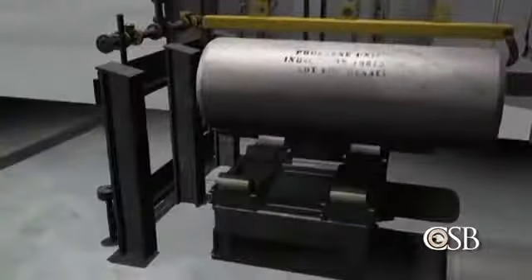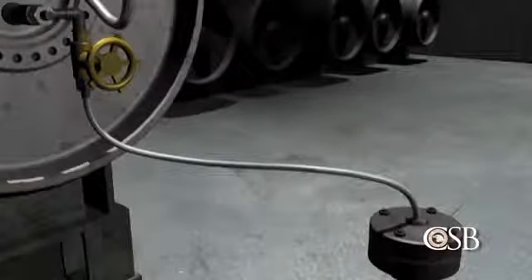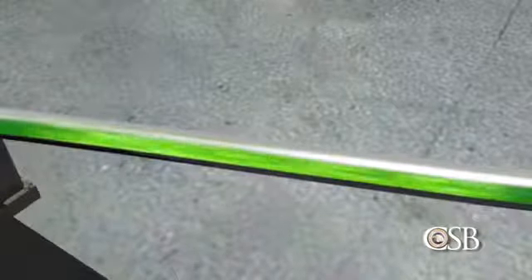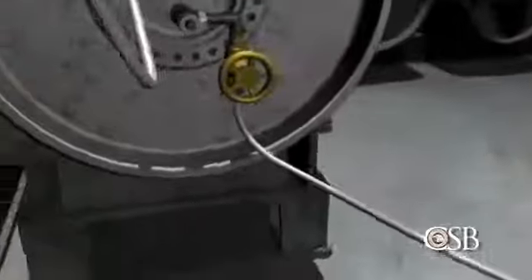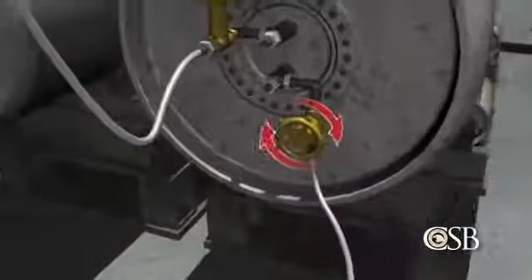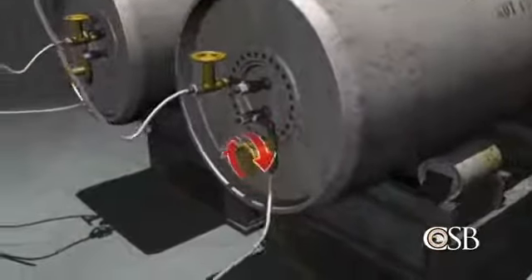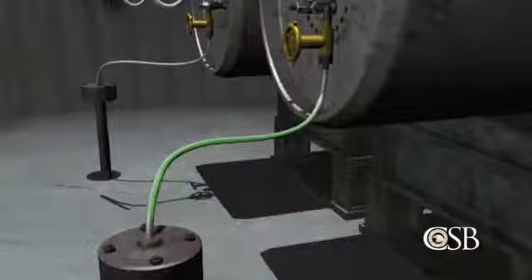On the day prior to the fatal Phosgene release, operators were experiencing flow problems with one of the hoses and began switching between cylinders to avoid disruption to the chemical process. In the course of switching cylinders, the valve was closed on a partially full cylinder. However, the hose was not purged, allowing pressure to build as the liquid Phosgene inside warmed up.